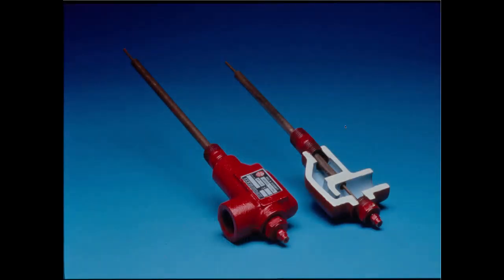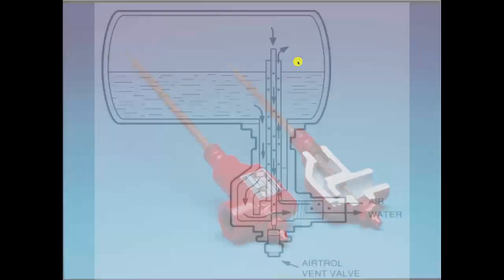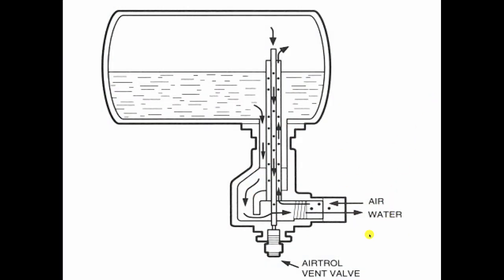So if we can prevent this gravity circulation, we can prevent the loss of that air cushion. The way that's done is to use this device that B&G came up with — it's called an Airtrol tank fitting. It works by having this little cup and a tube that sticks up above the water level in the tank like a periscope. On the job, it looks like this. We separate air down below with an air separator, it rises up by buoyancy and goes up into the tank, but the hot water rising up with it can't go any higher than the top of the tube, which is higher than the water level. And the hot water coming up can't get under this cup because hot water won't sink — it'll only go up. So by setting it up this way, you effectively stop the gravity circulation between the tank and the system, and you won't lose the air that's in the tank.